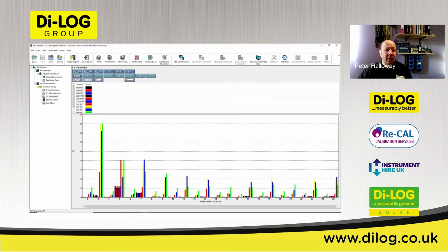So you can see here we're looking at the first 25 harmonics, and you can see the 5th are high, the 7th are high, and can you also see there that the 11th and 13th have got some. Now this does correlate with what the manager was saying, because on this particular site they had quite a lot of variable speed drives - they had far more 6-diode variable speed drives, which will give you 5th and 7th harmonics, as opposed to the 12-diode variable speed drives, which will give you 11th and 13th. So you can see why you've got more of a problem with 5th and 7th, for instance.